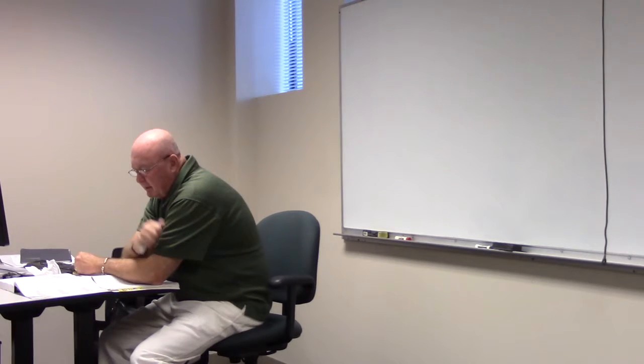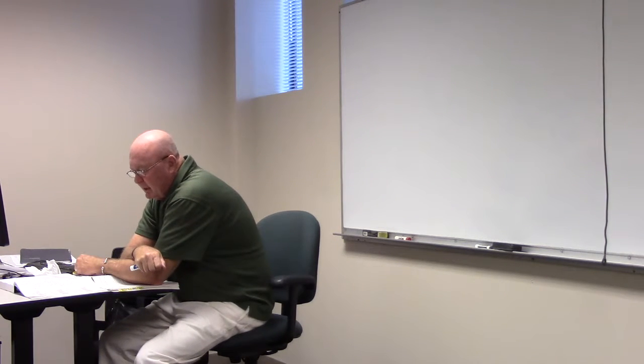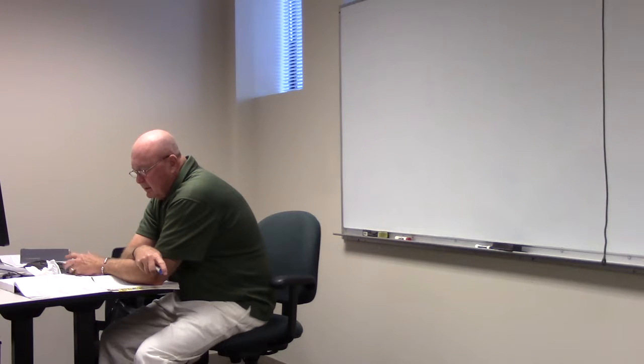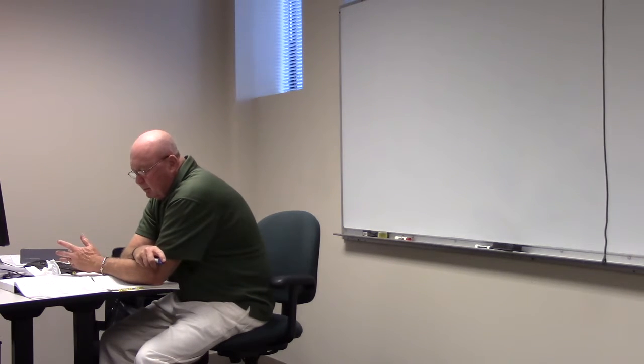Okay. Looking at a little green note there. Any loads that are continuous are multiplied by 125%. We've been talking about that. All others is 100. Next section, outside lighting loads. Outside lighting loads are calculated by multiplying the rating in VA by the number of fixtures. So that's pretty easy, 220.14(D). Example, we got 30 outside lighting fixtures. They're each rated 250 volt amps, which also stands for what? Watts, right? Including the ballast, these lights are rated 240 volts.